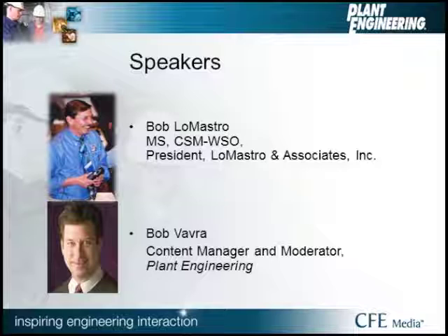Yeah. OSHA's always considered 70E sort of the de facto guidelines that they're going to use in establishing this. They're saying we're not going to be able to do any better than this, so we're going to defer to 70E as the standard. I think that is a better word than law at this point. Exactly. What our listeners need to understand is OSHA has to write regulations for every type of environment. They cannot get into the details that an industry specialist like the National Electric Code or the NFPA is capable of doing. Yeah, and it's actually proven over time that OSHA has been very responsive and very accepting of 70E and the work that's being done by NFPA to get this standard in place and to continue to improve it. I mean, we all know that 70E is not a couple of tablets brought down from the mountain.